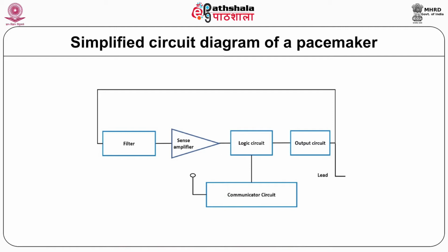A problem with the sensing of electrical activity is that the body essentially creates a lot of electricity, and it is commonly seen that the activity of the ventricles generally drowns the signal generated by the smaller atria. A way of removing this ventricular noise is to filter the signal. Filtering enables us to find the signal of choice from the electrical activity.